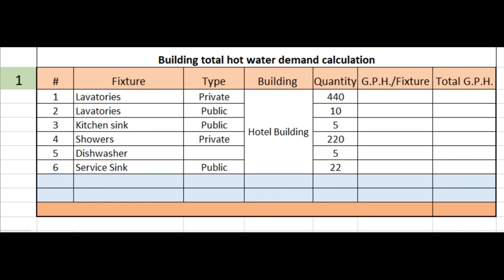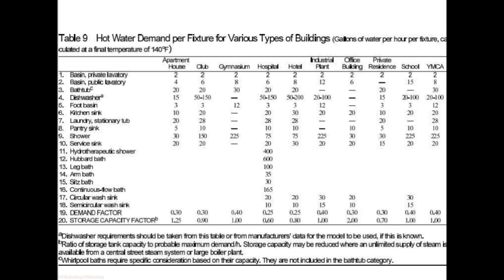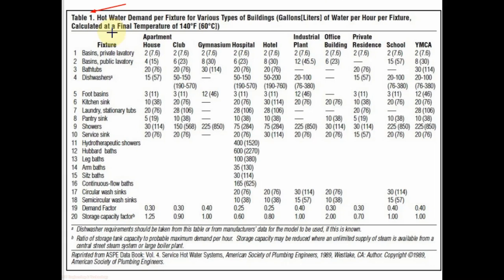For the calculation of hot water demand, let us make an Excel table showing fixture name, their type, building type, and fixture total quantities. For hot water demand per fixture for various types of buildings, there are two tables: one from ASHRAE Table 9, and Table 1 from the American Society of Plumbing Engineers, to find the hot water demand per hour per fixture for all types of buildings.